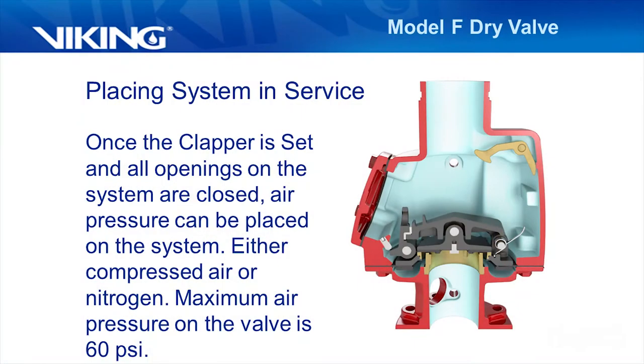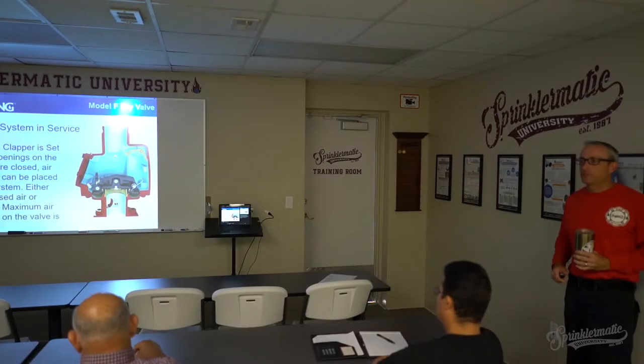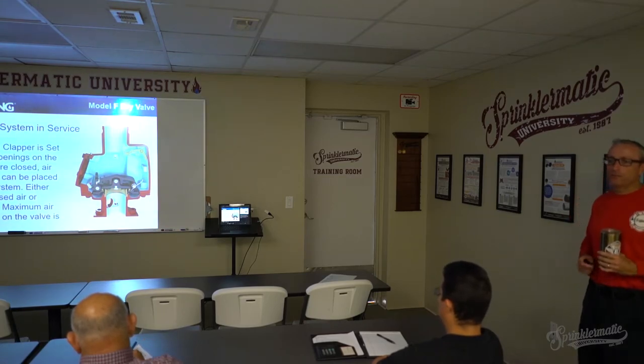All right, so then we've got to pressurize the system with the air, obviously. So the clapper has to be set. The air is either going to be compressed air or nitrogen. I think more systems are trying to go to nitrogen because...